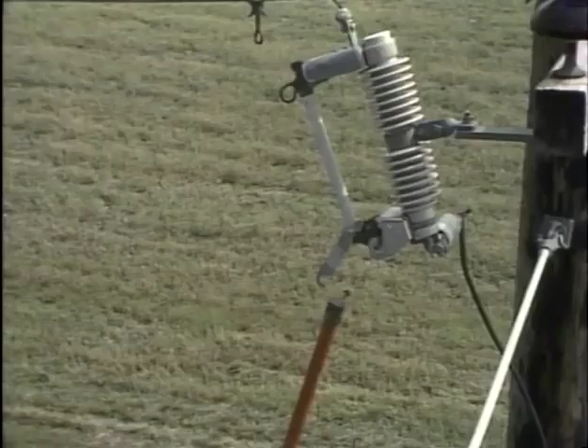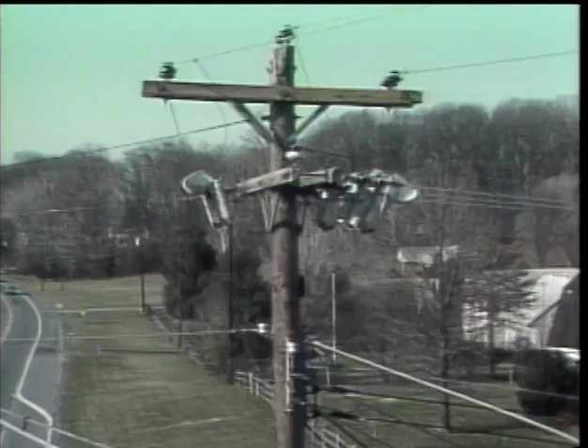To de-energize and isolate a circuit under load, a hot stick can be used to push up on the latch. Pushing up on the latch breaks the fuse and causes the switching arm to spring open. Because the circuit is broken by the fuse, any arc is contained and extinguished within the fuse tube. Other load break switches can have arc breaking devices attached to them. These devices can help distinguish a load break switch from a no-load switch.